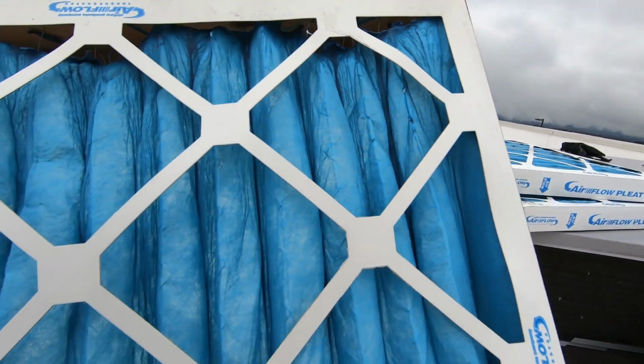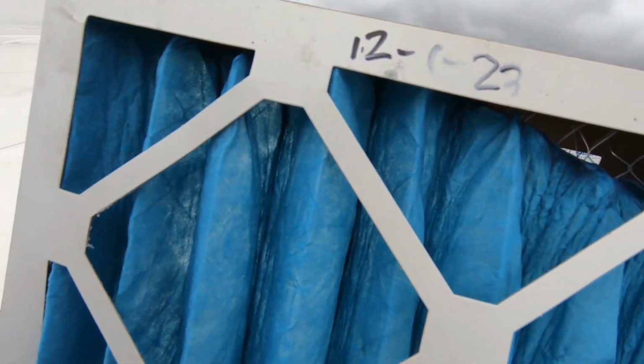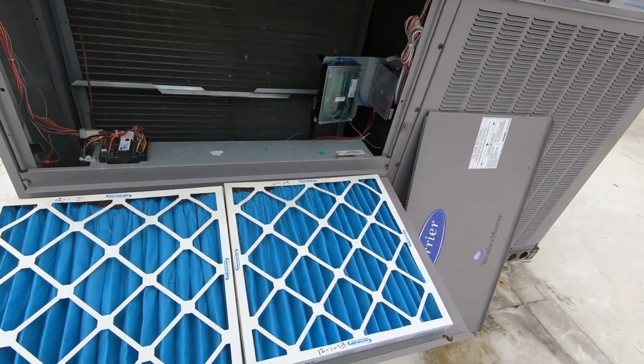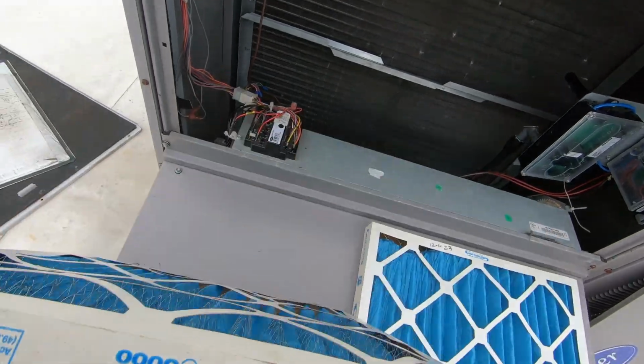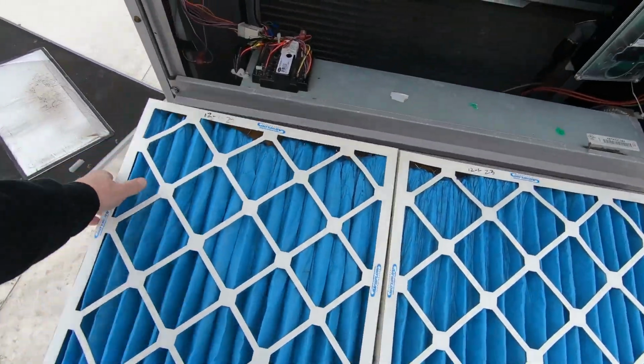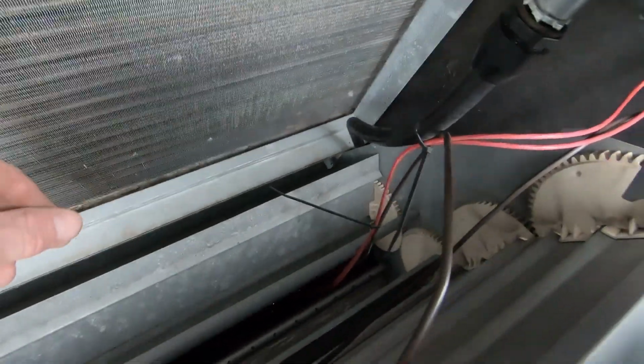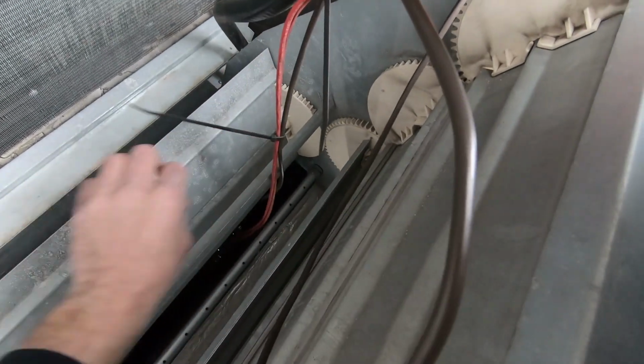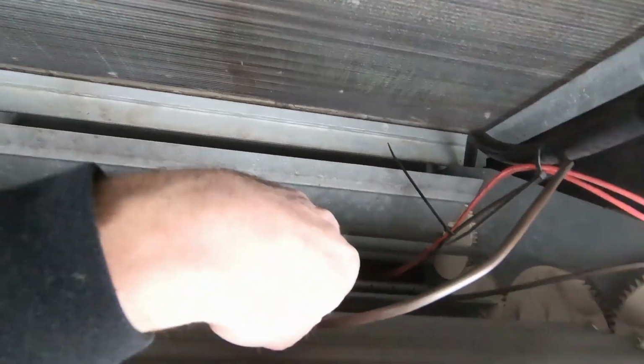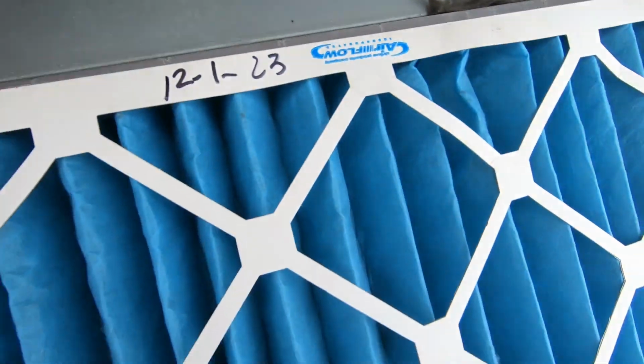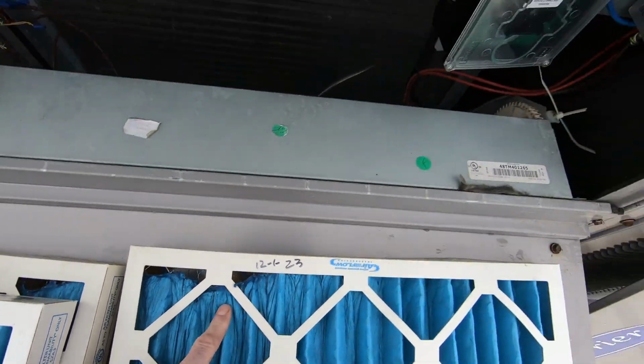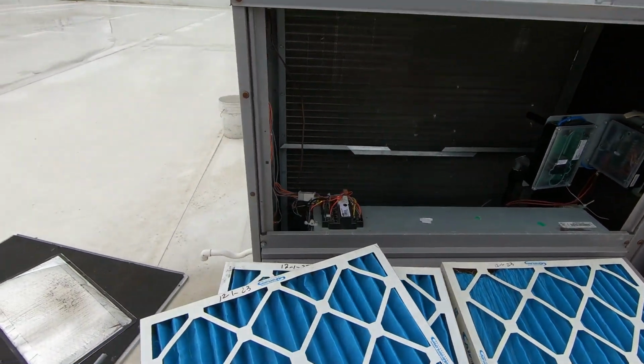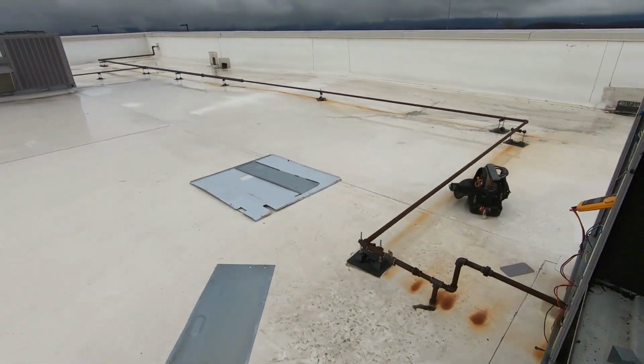Good Lord. These got so hot that it melted the fiberglass. They've only been in since December 1st. So that's 2 months. I doubt they looked like that when they were put in. They're real lucky there wasn't a fire here. A serious one. Look at this. They ran their wire right through the economizer. How's the economizer supposed to close? You just pinch the wires? Unbelievable. Wires run through the economizer. Melted filters. Limit bypassed. Belts off. Could have been real bad.